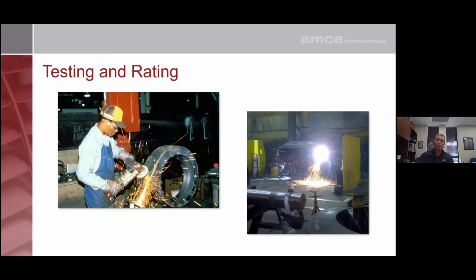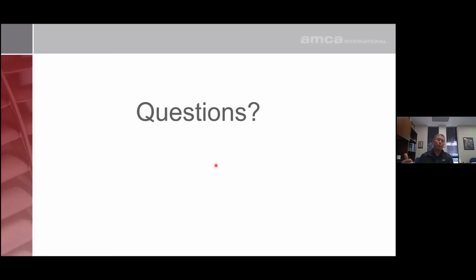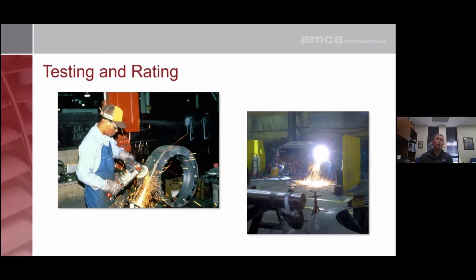Well, basically, every 3 years, AMCA sends us a request to check test a fan. So let's say we have a class 3 fan that's been certified. AMCA will send us a letter saying, hey, I need to have a size 27-inch fan. Send it to me, and we're going to verify that that fan performance meets what your catalog rating is. Again, plus or minus 2.5% flow pressure, 5% on energy consumption.